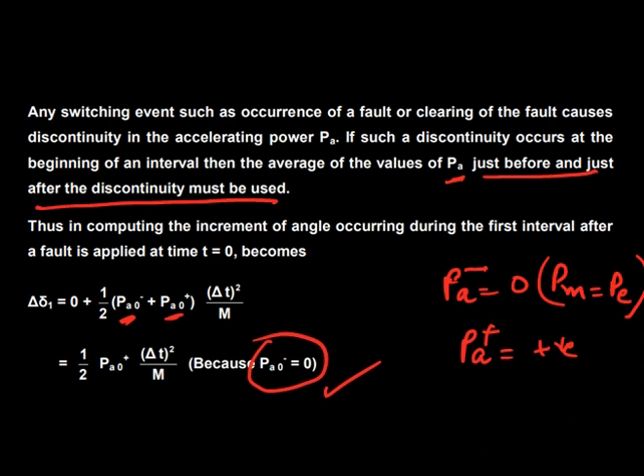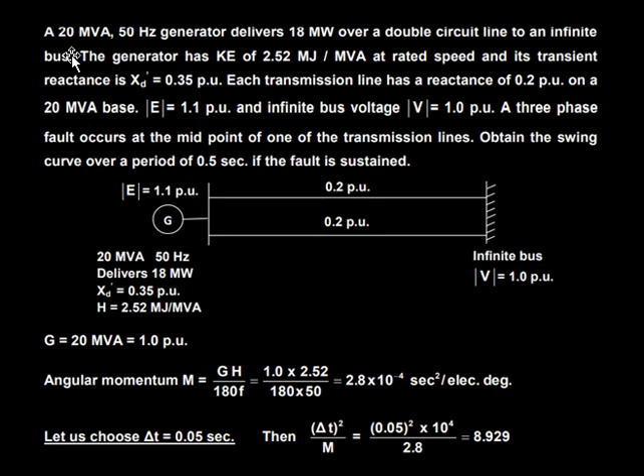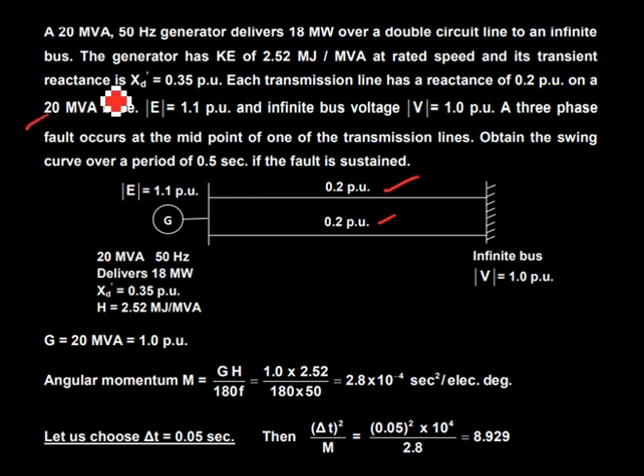Now let's take up an example to understand this. A 20 MVA, 50 Hz generator is delivering 18 MW over a double-circuit line to an infinite bus. The generator has a kinetic energy of 2.52 MJ/MVA and a transient reactance of 0.35 per unit. Each transmission line has 0.2 per unit reactance on a 20 MVA base. The generator terminal voltage is 1.1 per unit and the infinite bus voltage is 1.0 per unit. A three-phase fault occurs at the middle of one of the transmission lines.